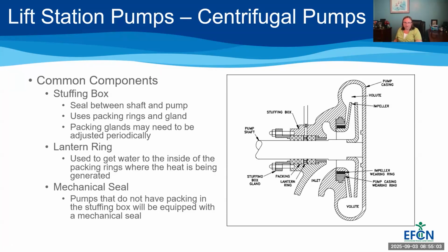Things like bearing lubrication frequency, checking the seals for leakage, observing the pump for any kind of excessive vibration, understanding your suction and discharge pressures, understanding packing spacing, and impeller placement. So use your study books, get familiar with these components, get familiar with the maintenance of these components. Pretty certain that you will see questions about these on any level 1 or 2 exam.